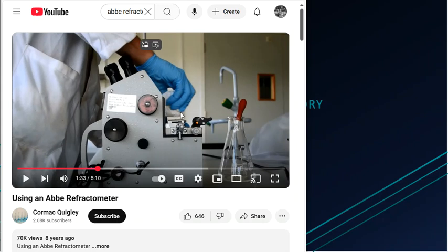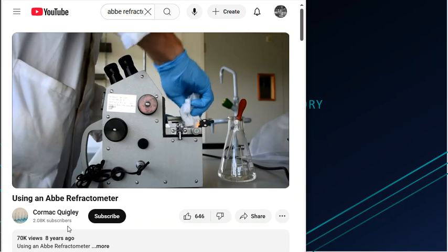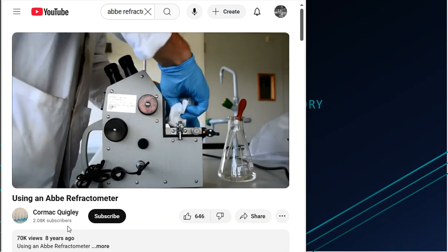And notice he said both sides of the prism. There is a top surface contact and a bottom contact that touches your sample. So a lot of people will clean the bottom, but they don't clean the top one. And if not, you're doing cross-contamination. So you want to make sure that you clean the top portion of the sample compartment as well as the bottom one. Give it a second or two to dry, and it's ready for use.